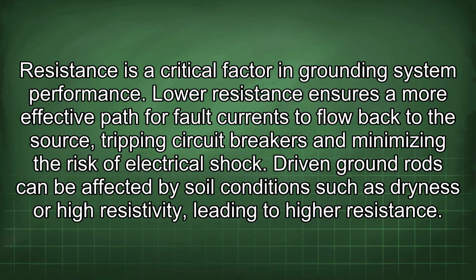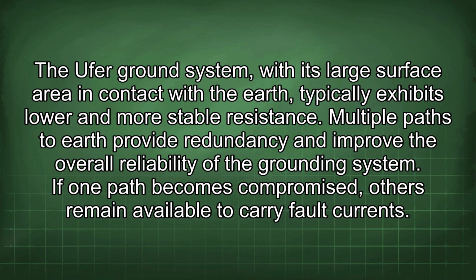Resistance is a critical factor in grounding system performance. Lower resistance ensures a more effective path for fault currents to flow back to the source, tripping circuit breakers and minimizing the risk of electrical shock. Driven ground rods can be affected by soil conditions such as dryness or high resistivity, leading to higher resistance. The Ufer ground system, with its large surface area in contact with the earth, typically exhibits lower and more stable resistance. Multiple paths to earth provide redundancy and improve the overall reliability of the grounding system.